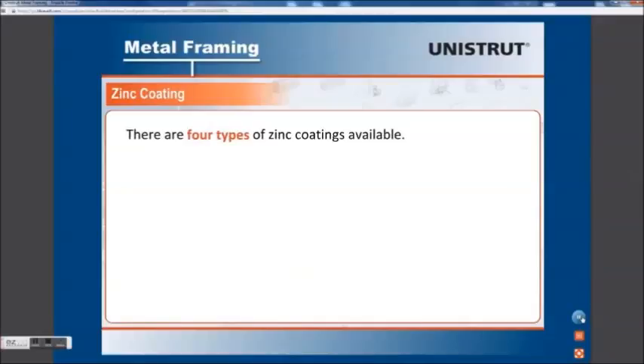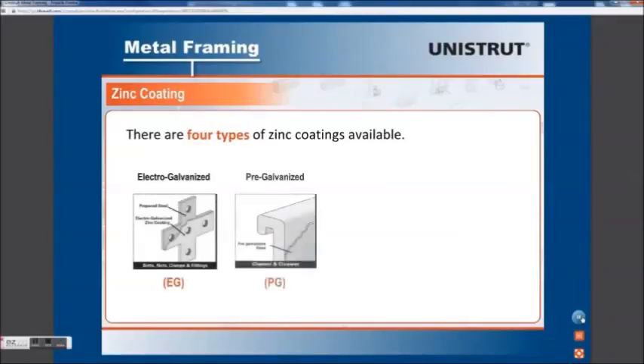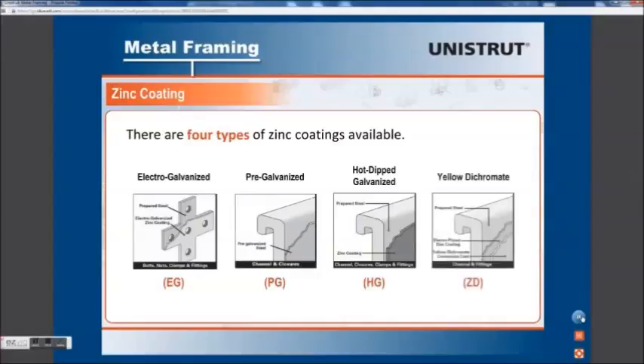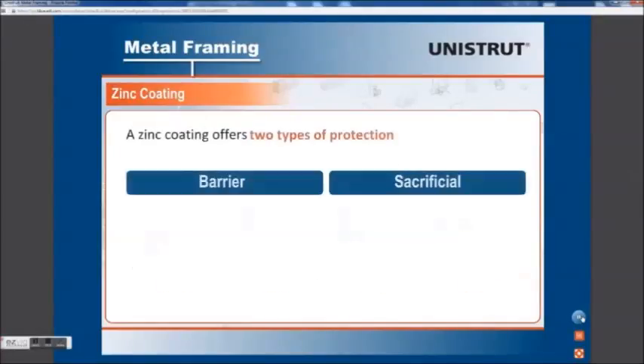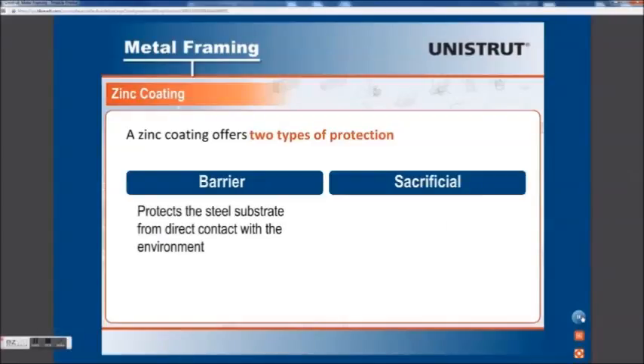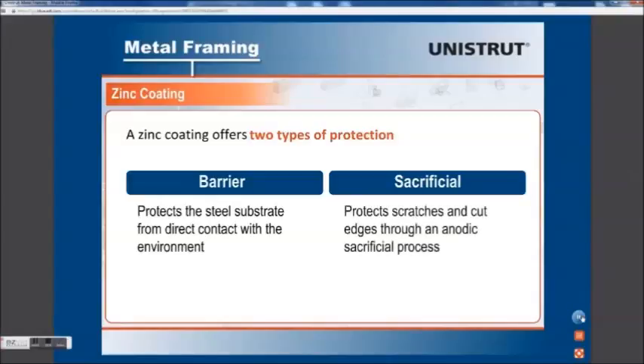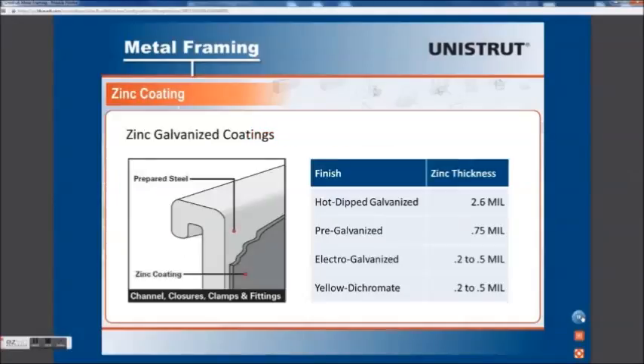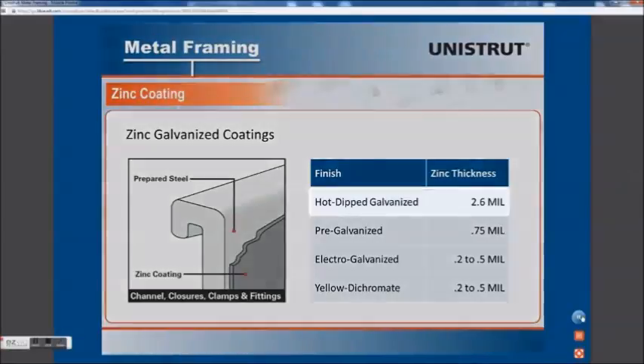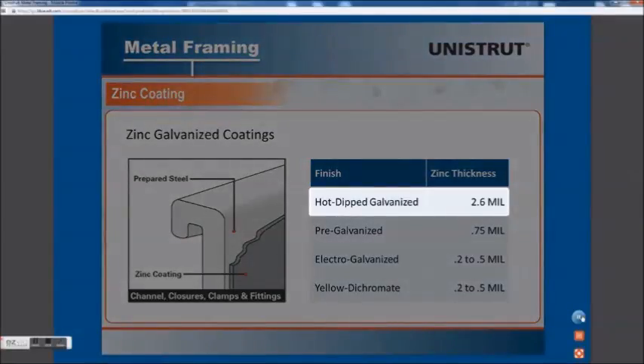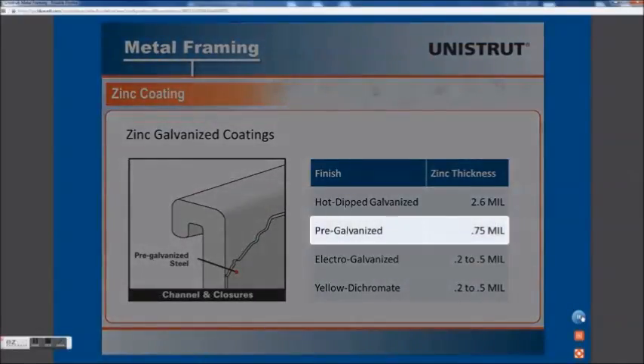There are 4 types of zinc coatings available: electrogalvanized, pre-galvanized, hot-dipped galvanized, and yellow dichromate. A zinc coating offers 2 types of protection: it serves as a barrier to protect the steel substrate from direct contact with the environment, and it protects scratches and cut edges through an anodic sacrificial process. The service life of zinc coating is related directly to its thickness. Hot-dipped galvanized finishes offer the greatest protection and are ideal for harsh outdoor environments, such as power stations. Pre-galvanized finishes are generally used for everyday building construction.